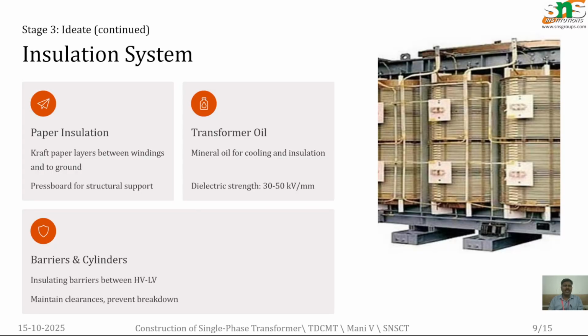And next, in the insulation system, mainly we are using paper insulation between the windings. And the transformer oil can be used. Here the transformer oil has a dielectric strength of 30 to 50 kilovolt per mm, so based on that we can use it in the transformer. It can be used for insulation as well as cooling. Paper is only used for insulation, and the oil can be used for insulation as well as cooling purposes. And barriers and cylinders can also be used. Here also we can maintain the insulation systems.